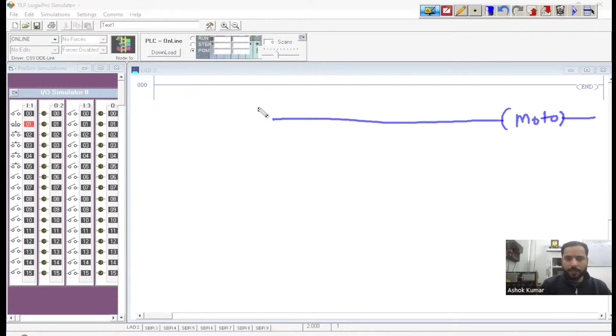So you have a sensor or a button. You want when the sensor is on or a button is on, the motor should be on. When the sensor is off, the motor should be off. So what do you have to do? Simply take a NO contact, give the address I:1/2, give the output address O:2/0. Make sure to connect the motor with this output and the sensor with this input.